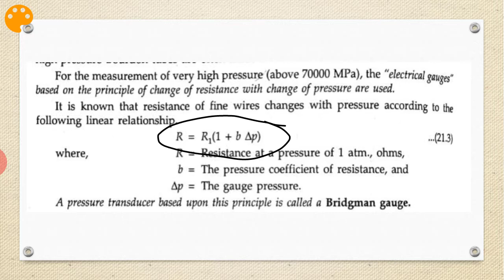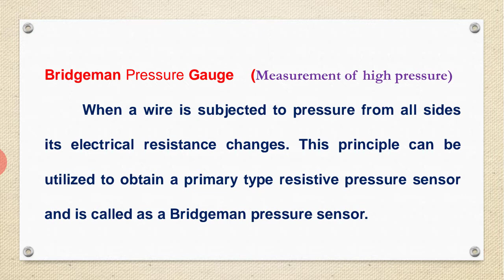The equation is given here: R is equal to R1 times (1 plus B delta P). R is the resistance at a pressure of 1 atmosphere in ohms, B is the pressure coefficient of resistance, and delta P is the gauge pressure. So once again, the basic principle: when a wire is subjected to pressure from all sides, its electrical resistance changes. This principle can be utilized to obtain a primary type resistive pressure sensor, called a Bridgman pressure sensor.